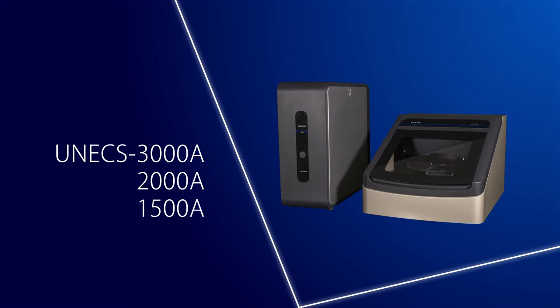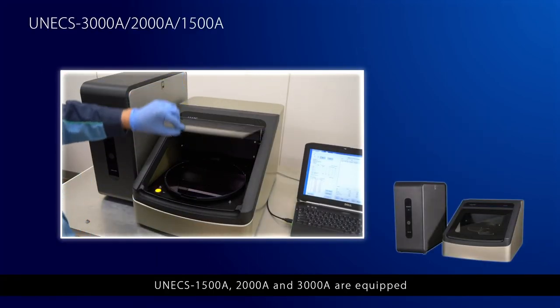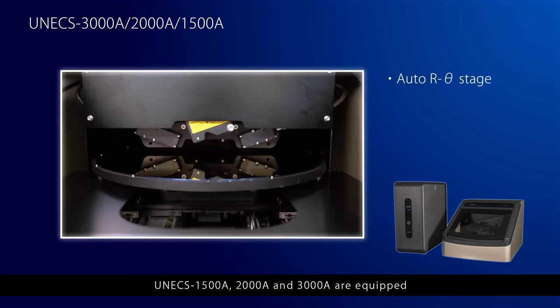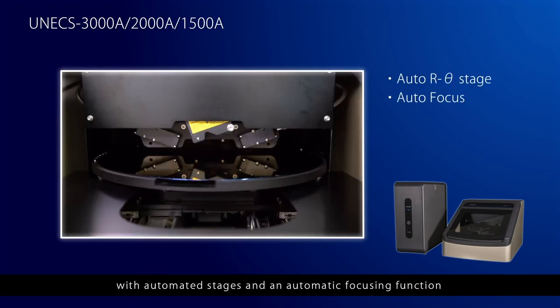UNECS-1500A, 2000A and 3000A are equipped with automated stages and automatic focusing function, making it possible to perform automapping with an extremely high throughput.